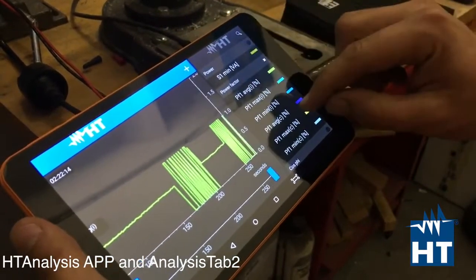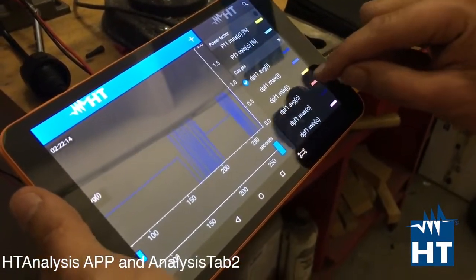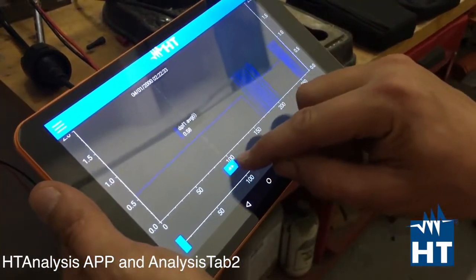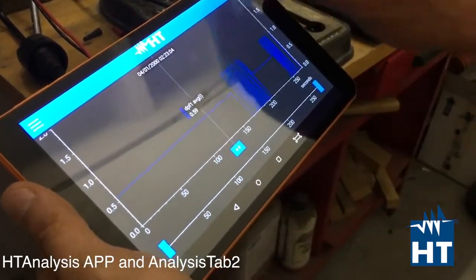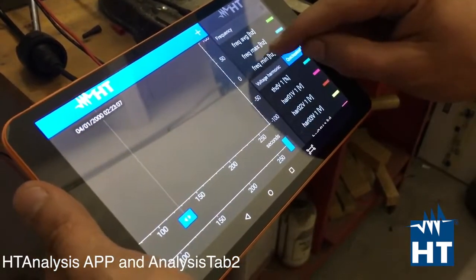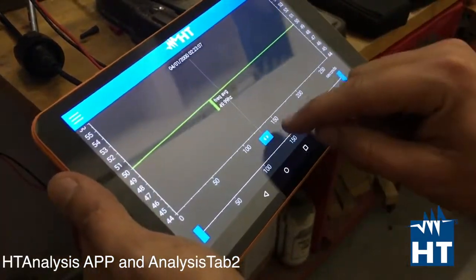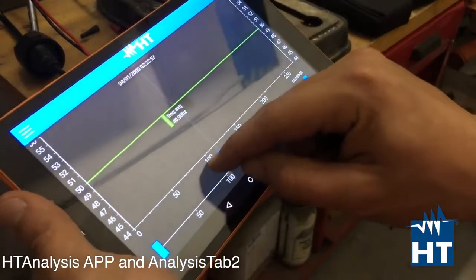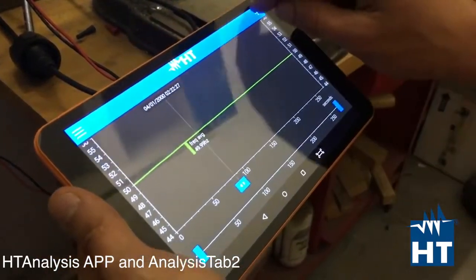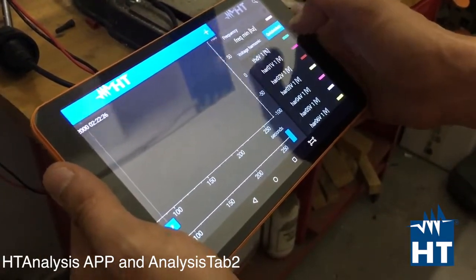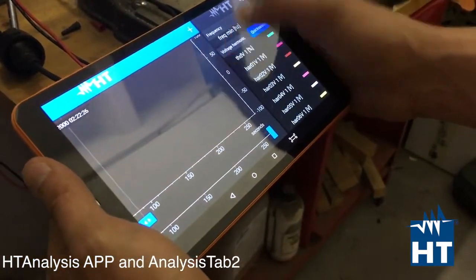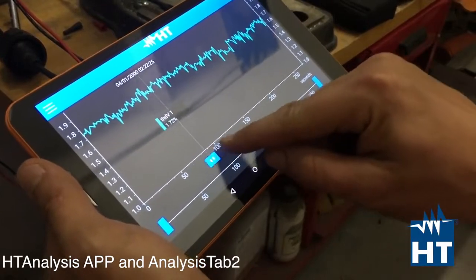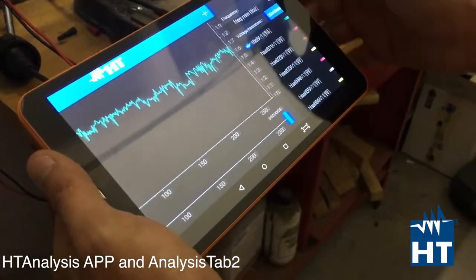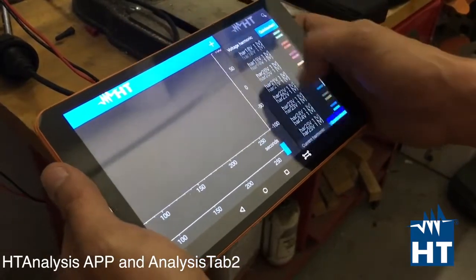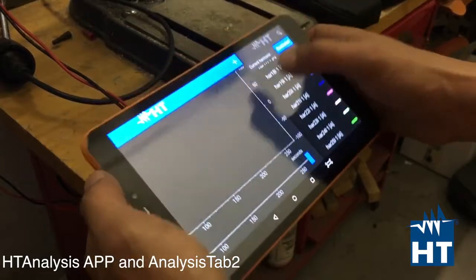It's floating because I think I switched it off. The cos phi, which is pretty stable, 0.58. The frequency, you can analyze the frequency, was pretty much stable from 49.98 to 50. You see these days the frequency is no longer stable at 50, but varies over time. And you can see the THD, the total harmonic distortion of the voltage, for example. You will see it's pretty much stable. Then here we have all the harmonics of voltage and so on.